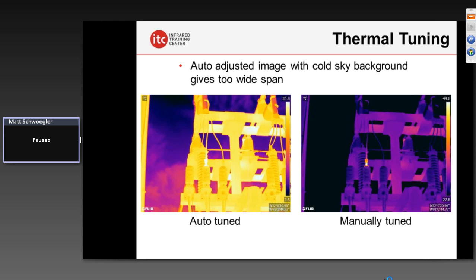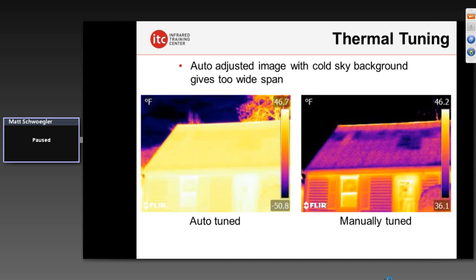We work on this as part of training — getting well-thermally-tuned images as part of the certification process. And it's true for those in buildings too. If you're looking for missing insulation on the roof of a residential home, the manually-tuned image on the right provides much better detail — we actually see that most of that roof appears to be uninsulated. But in the auto-tuned image where we haven't adjusted the scale, we get most of the sky in the frame and that nearly 100-degree span causes us to lose a lot of contrast on the surface of the roof, making it impossible to diagnose what's happening.